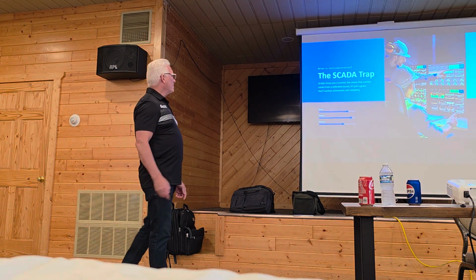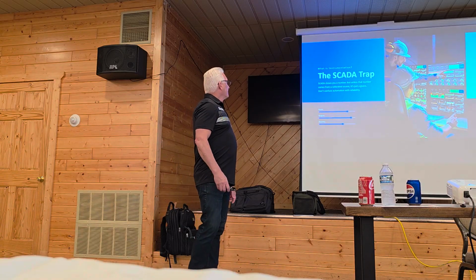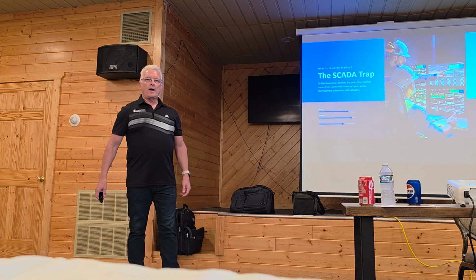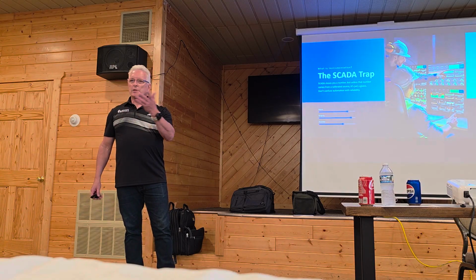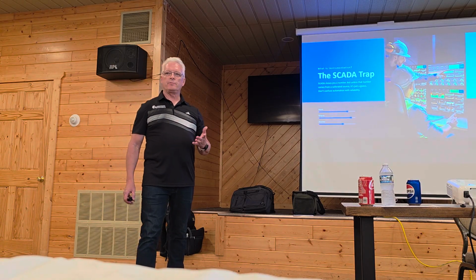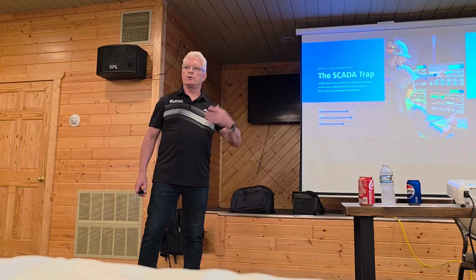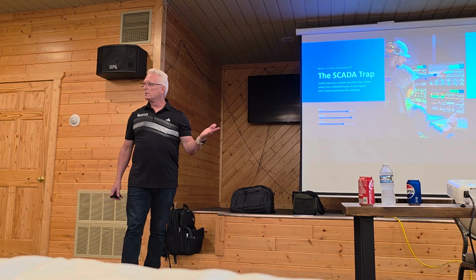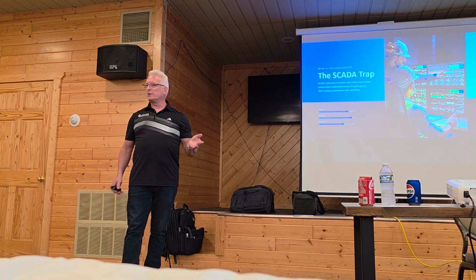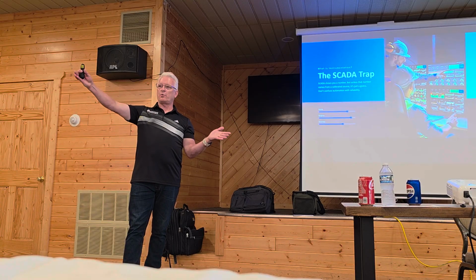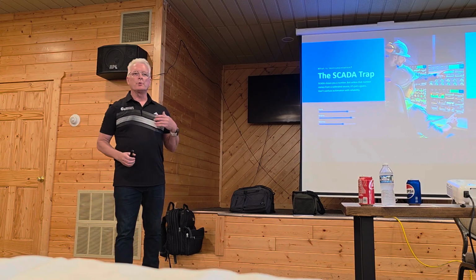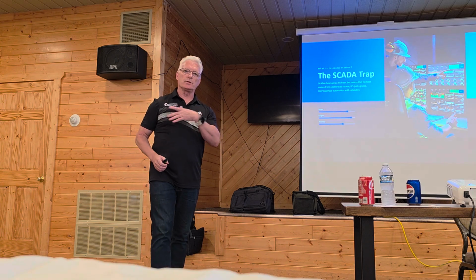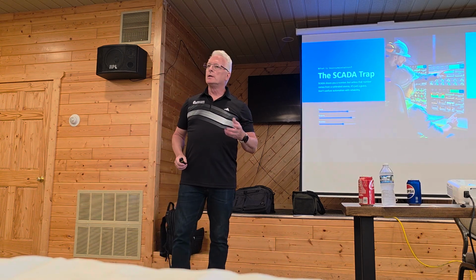So the SCADA trap, almost what I was just talking about. If I have that flow meter, and I always talk about flow because everybody's got flow. So if we have that flow meter and it's set up 0 to 1,000 again, but your SCADA is set up 0 to 2,000, it's not going to display right because your span on the SCADA is twice as much as the flow meter. So when we first go out and do meters or do a calibration of any piece of equipment, there's two things we do.